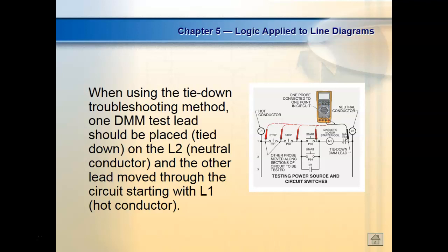Normally when we troubleshoot voltages, we take one lead. If it's AC, it makes no difference whether you put the black or red lead there because AC technically has no polarity — it's constantly swapping. DC, even with digital meters, if you're expecting positive you might see negative, but the voltage is still calculating exactly the same. I'll put my black lead one place and work all over the circuit — I understand that voltages are dropping.